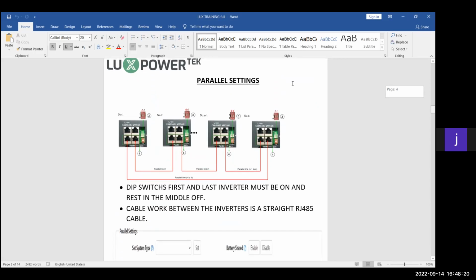Now this is where we get to our parallel system. To parallel these units, all that you're going to need is 2 or more, depending on the amount of units. Let's say there's only 2 units, then you'll need 2 straight RJ485 cables. So it's normal internet cables, as a lot of clients call it a LAN cable. So you only need a straight pinout configuration. The machine comes parallel ready. The machine comes with a dongle in the box, so you don't have to buy a dongle separately. All that you're going to have to buy separately is your communication cables, your LAN cables. They are fairly inexpensive, so it's not difficult to get a hold of normal straight comms cables.